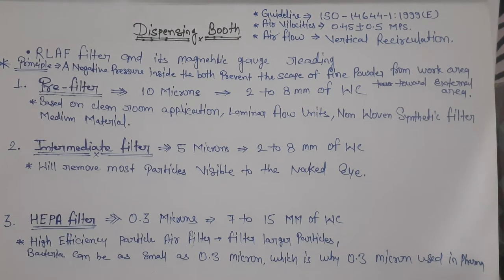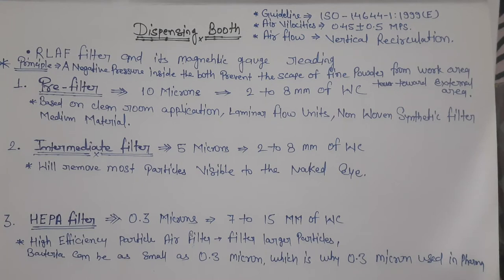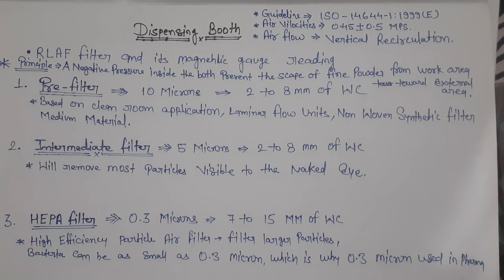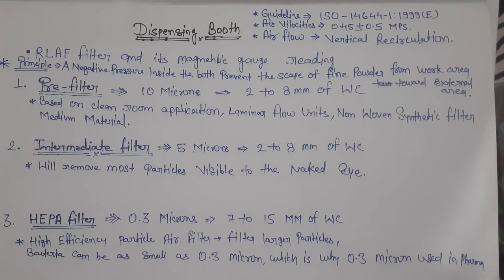Let's see about the first: pre-filter. Pre-filter size is 10 microns and manometric gauge reading is 2-8 mm of water column. This is based on clean room application, laminar flow unit, non-woven synthetic filter medium material. The second one is intermediate filter.